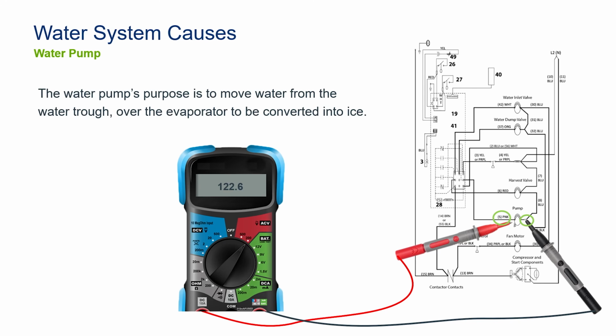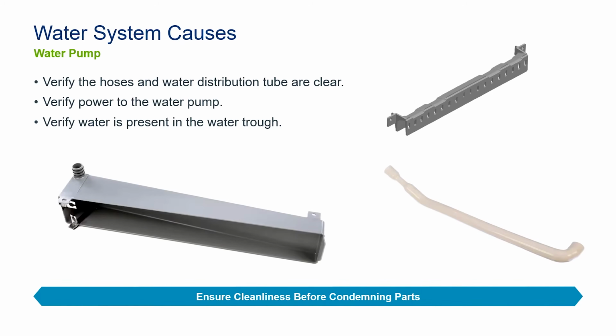That will lead to a service limit number 1, long freeze. If you don't move water over the evaporator for 45 consecutive minutes, 6 consecutive times, you didn't make any ice. You're going to end up dealing with a couple of service limits, really, but this will lead to service limit 1. If you wanted to check directly at the board because you couldn't get to your water pump for whatever reason, you could also go into the 9-pin connector at wire number 5. It's going to be a pink wire. And on this unit, it would be wire number 56.